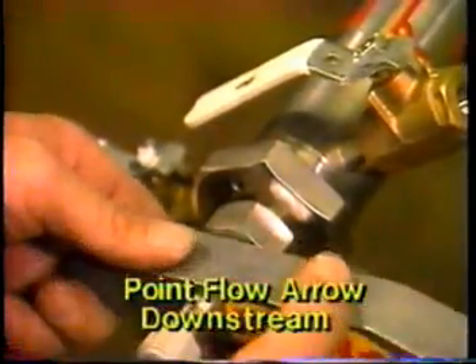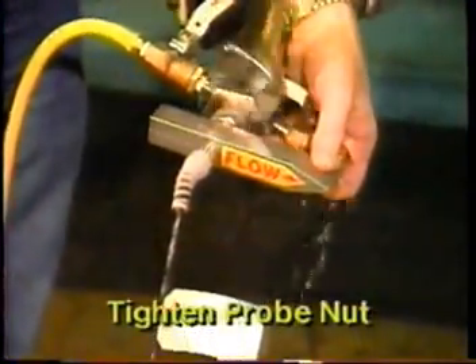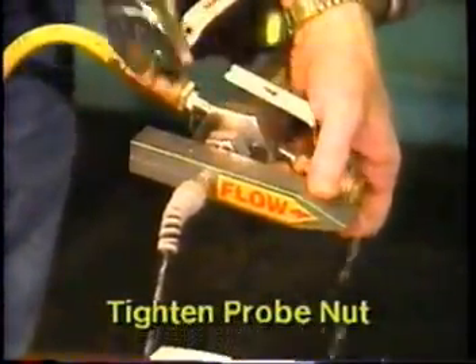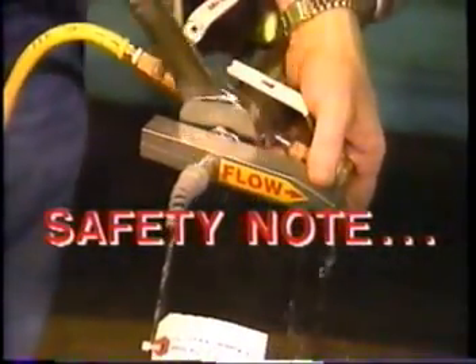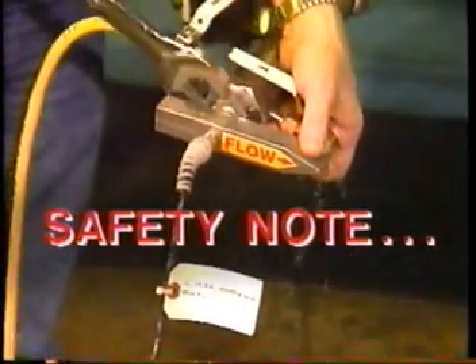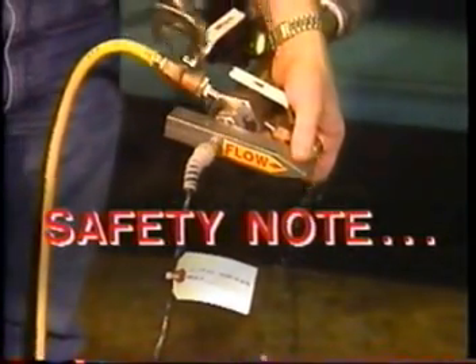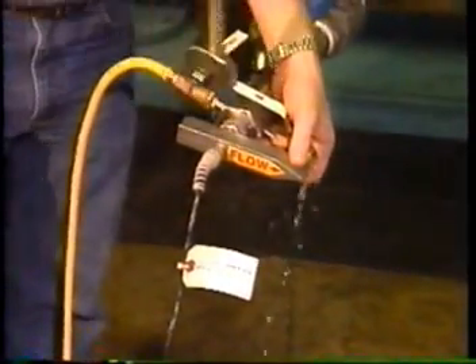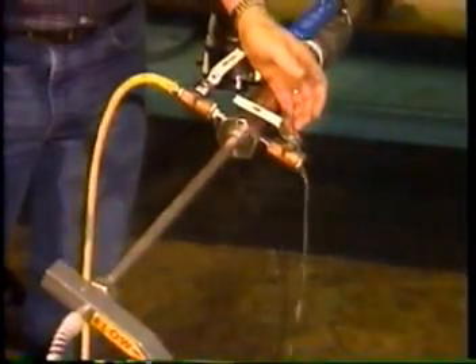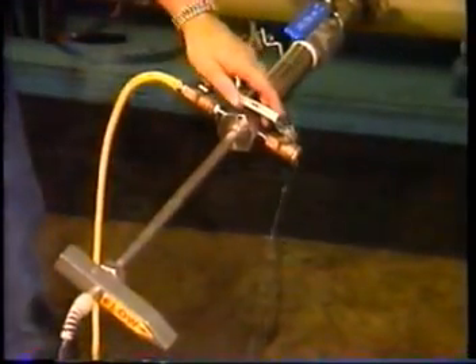Position the flow arrow to point downstream. Tighten the small nut over the probe extension. If these sequences are not performed precisely, the probe can be forcibly thrust out to the back of the extraction chamber by pressure in the stock line, possibly causing personal injury and undue stress to the equipment.